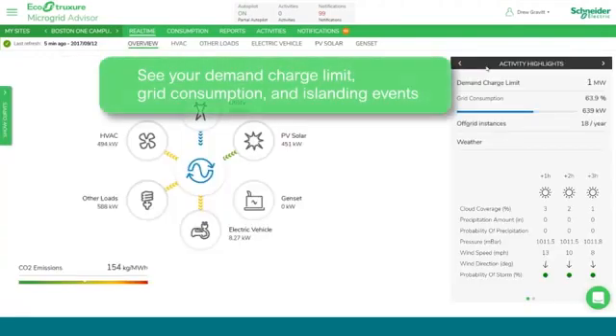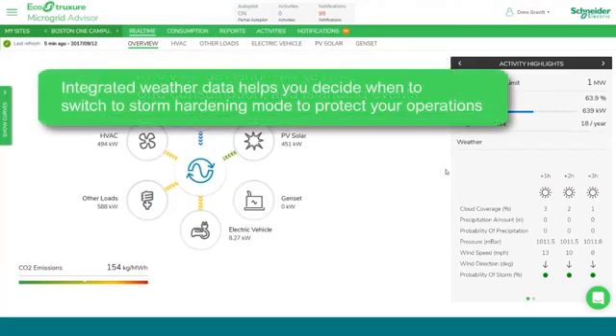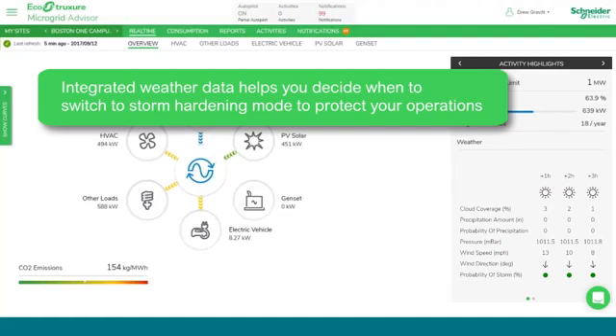Going back to the overview page, we can see some activity highlights. At the Boston One site, we have a demand charge limit of one megawatt. Today we're using about 64% of our total allowable power, and we've had 18 instances of off-grid islanded mode. Our weather service gives us utility-grade information and helps us predict any severe storms. EMA can potentially take the site out of optimization mode, remove it from doing any controls, and put it into a storm mode which would prepare the site for islanding, or potentially even pre-islanding the site before a utility grid outage.